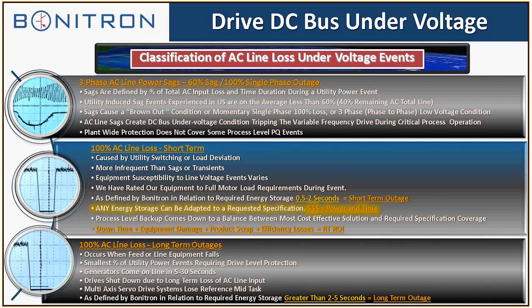Then we talk about long-term outages, 100% AC line loss, greater than 5 seconds. We used to say that short-term AC line losses would only go up to 2 seconds, but now we're using the heavy-duty boosters to use ultracaps for a longer outage time. So we can do ultracaps up to 5 seconds now. So now going back to the long-term outages, that's when over 5 seconds, up to 30 seconds, a minute, I've even had a request for 4 hours. That just means a great amount of energy storage.